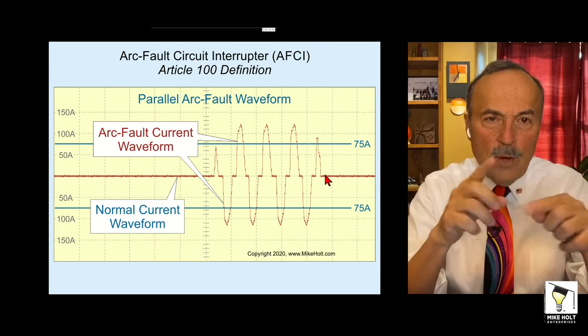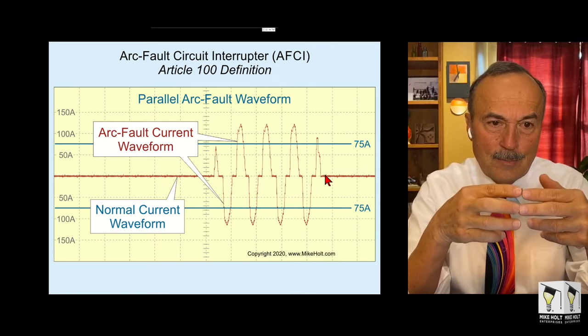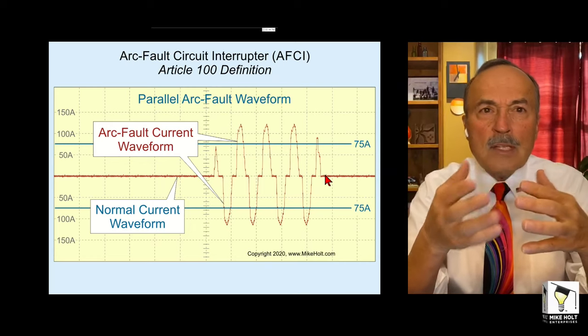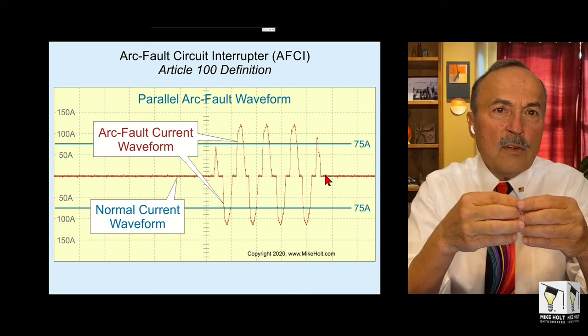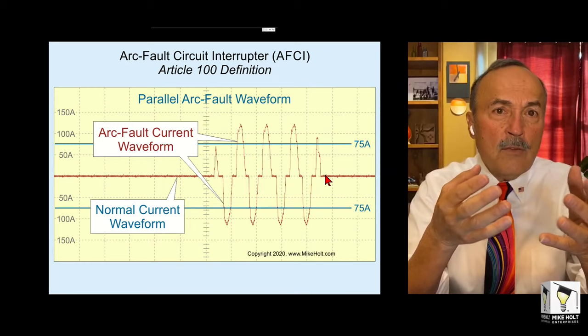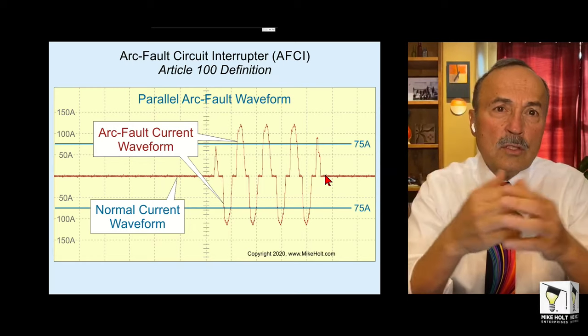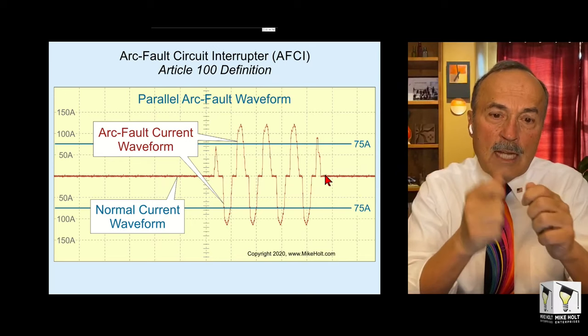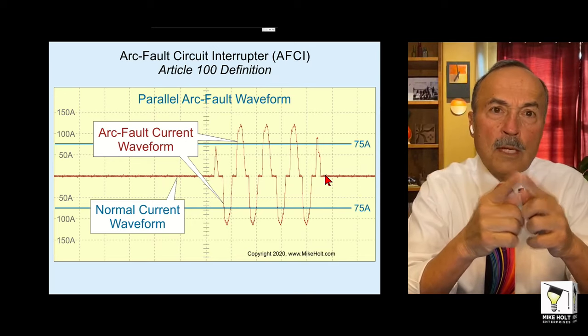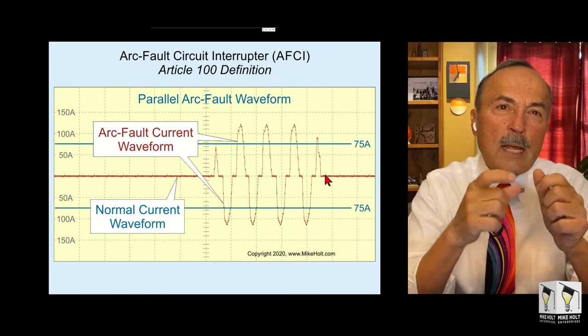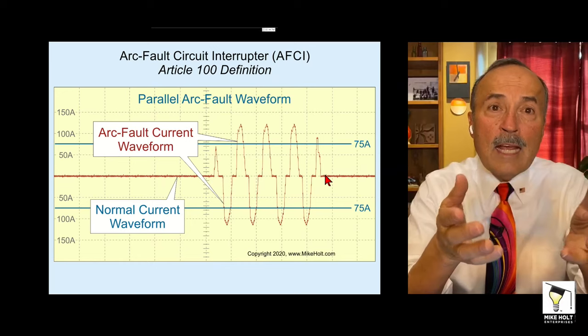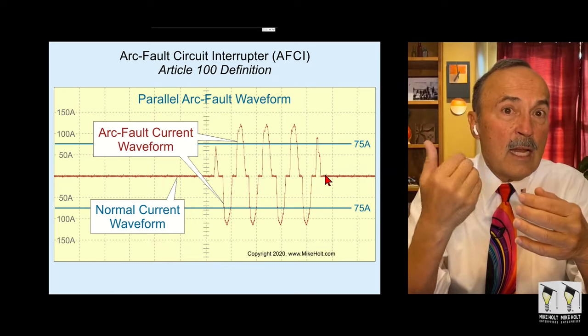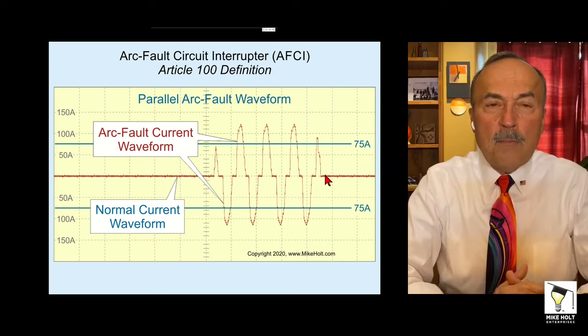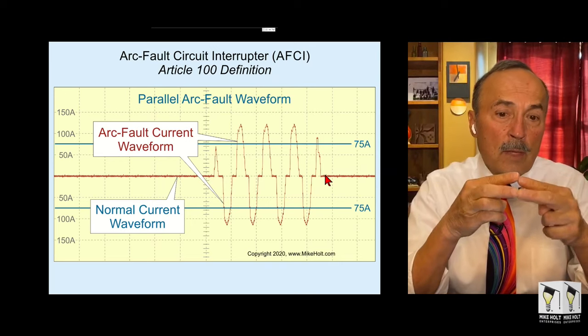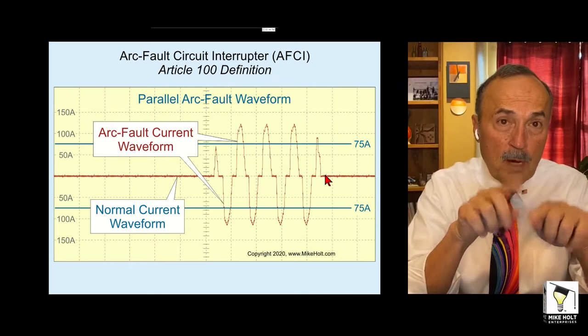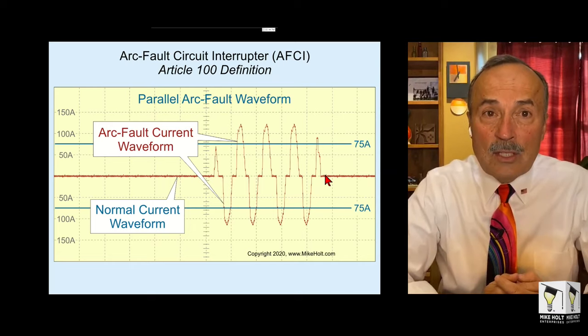And, of course, it can't use waveforms when it comes to series arcs. It works with a different type of proprietary method. It works off of something like a frequency, a noise. If you guys have been around years ago, cars used to have distributors, and every time the points open and close, you could hear the noise. Well, then they put a condenser on there. Or an AM radio where you see lightning, you can hear that lightning. So there are frequencies that the manufacturers use to detect series arcs. They use a computer internally to detect parallel arcs. That's called a combination AFCI.